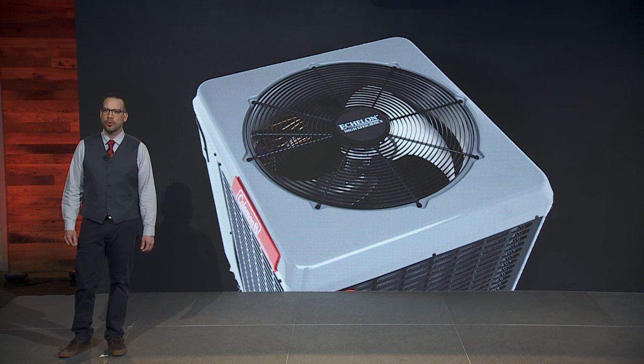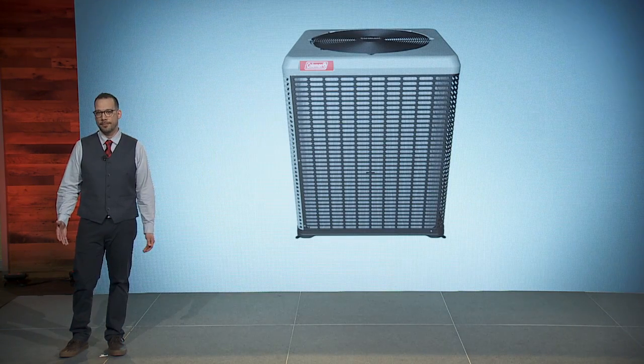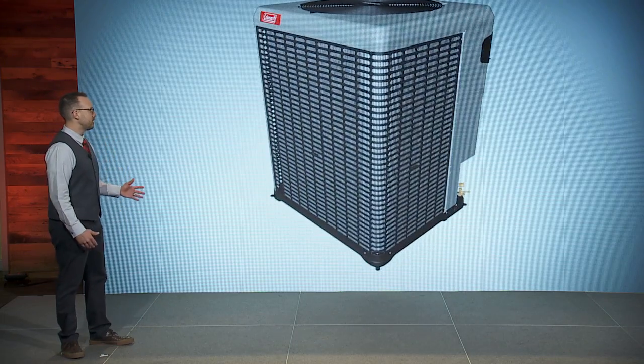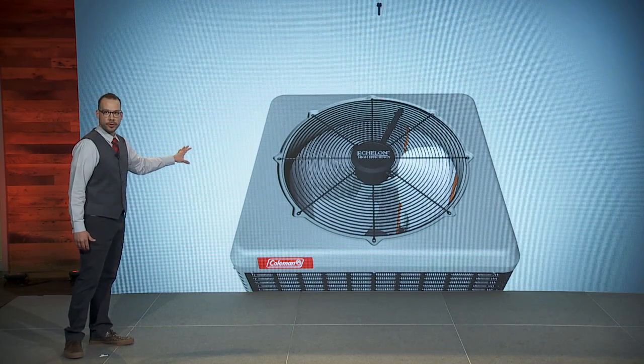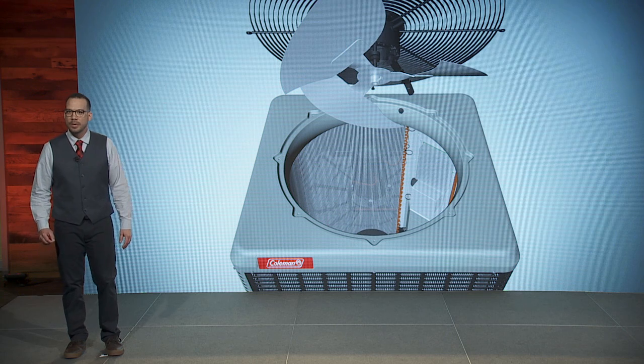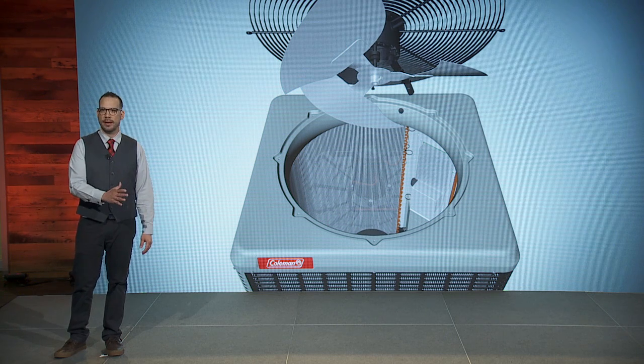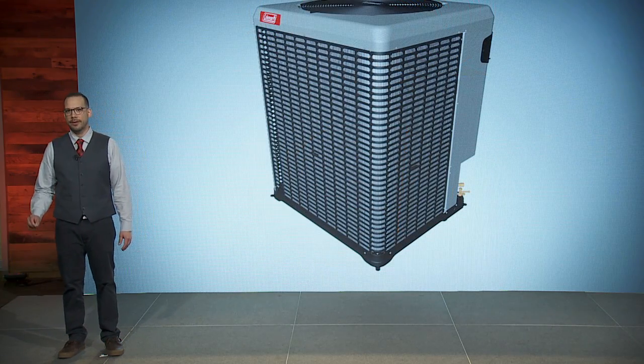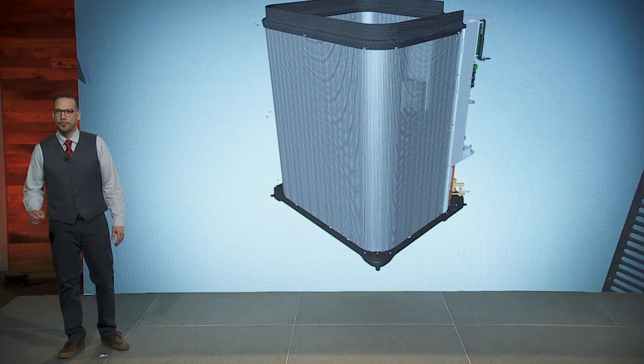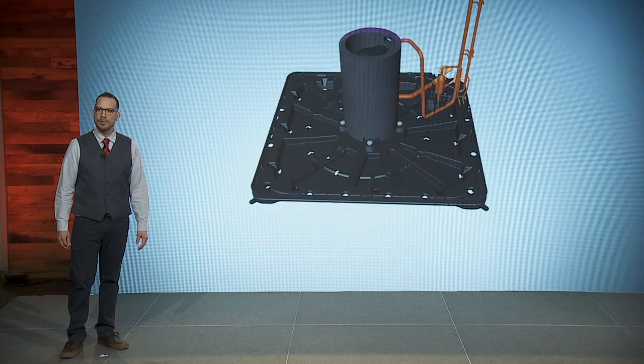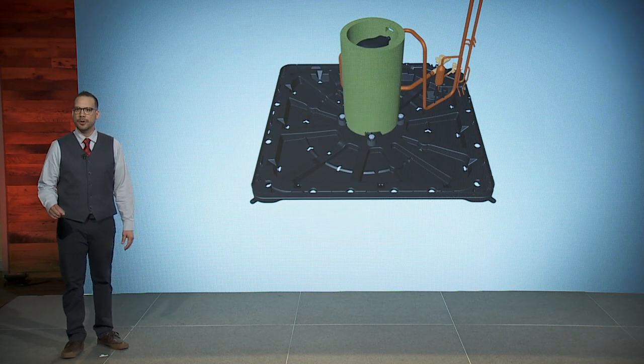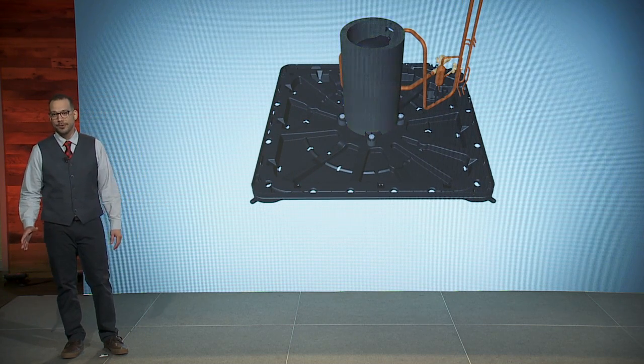This is made possible by being really purposeful in the design of three major components of the outdoor system. First, the fan. The fan is being silenced by both a variable capacity motor as well as a fan blade that we've designed to quietly sweep through the air while generating airflow required for reliable, efficient air conditioning. The compressor is outfitted with an enclosure that dampens sound waves before they can be distributed to the home or your neighbors.